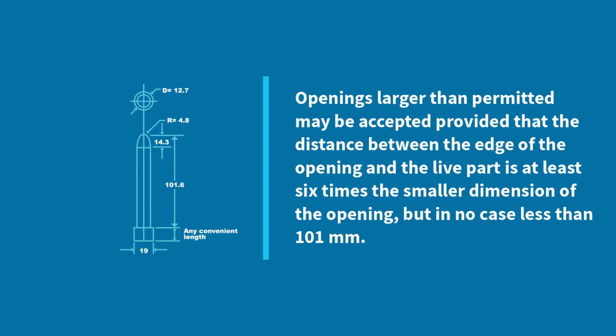Openings larger than permitted may be accepted provided that the distance between the edge of the opening and the live part is at least 6 times the smaller dimension of the opening, but in no case less than 101 millimeters.